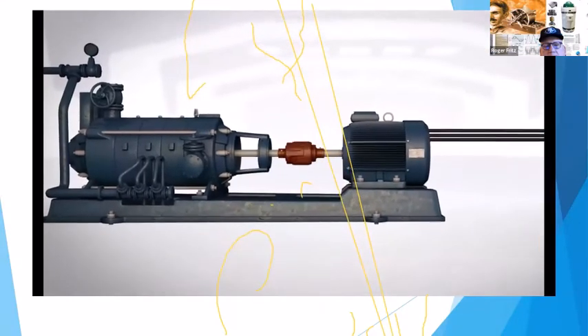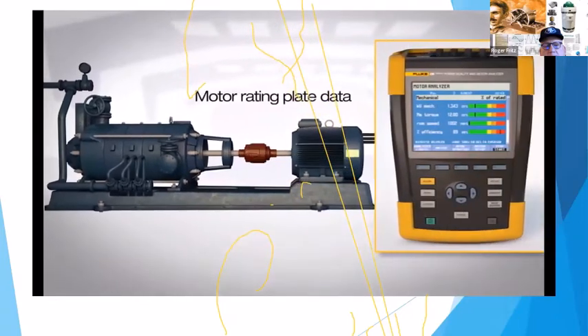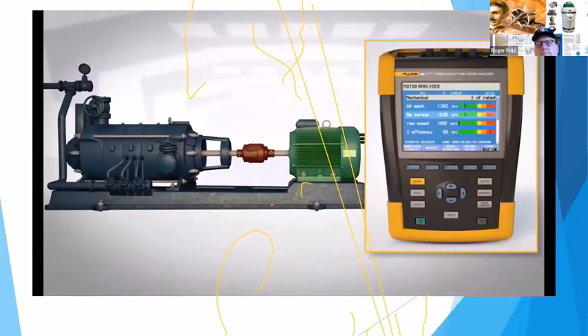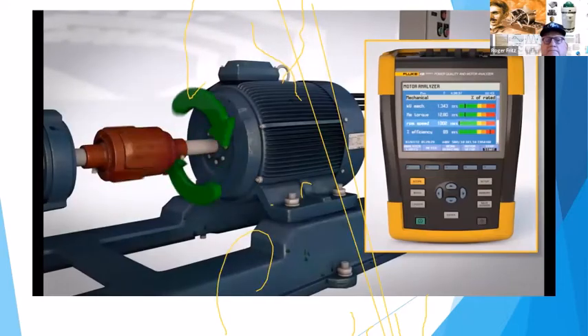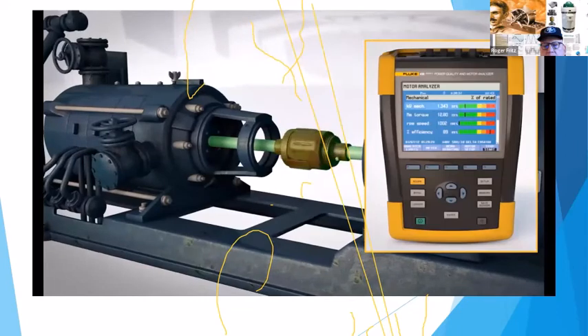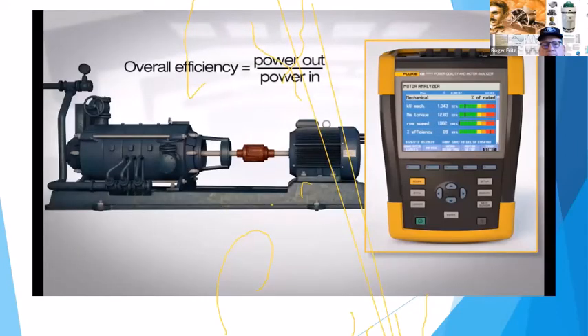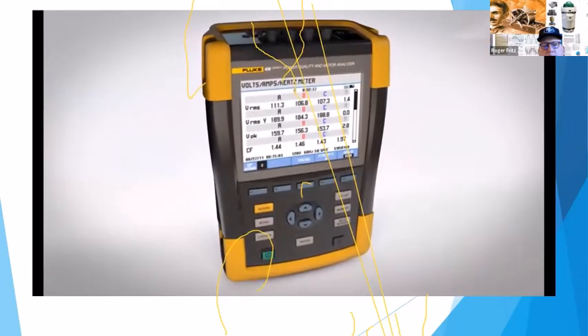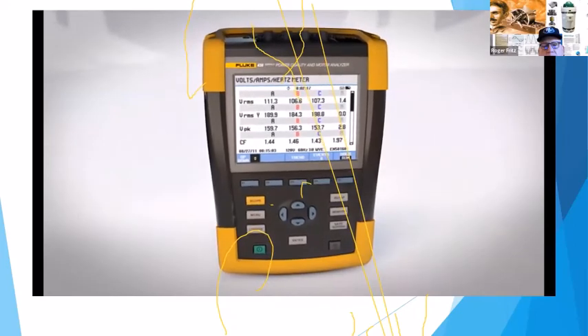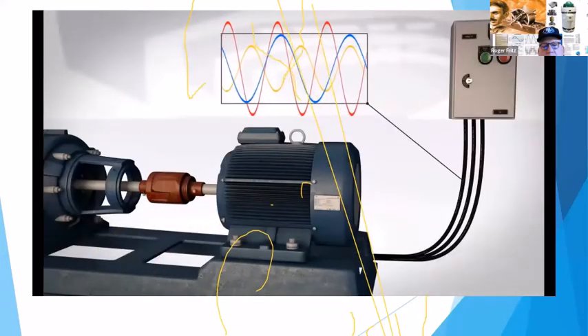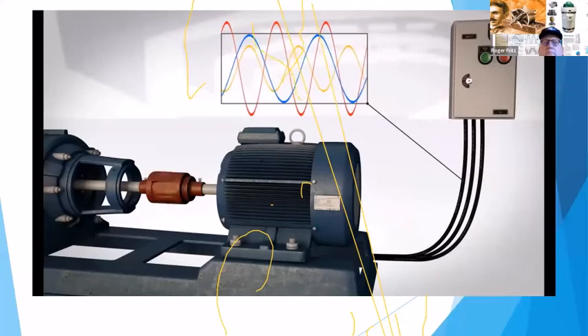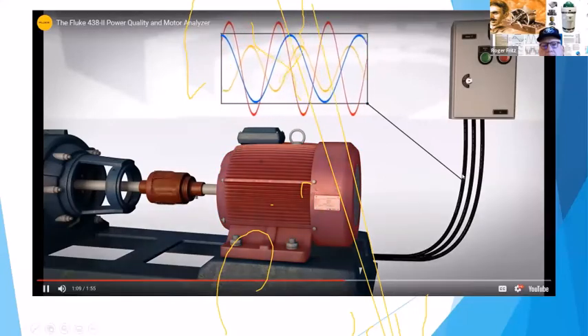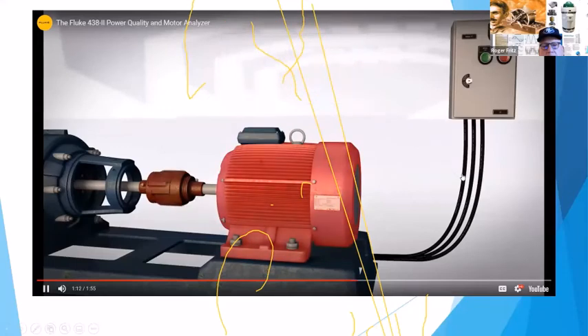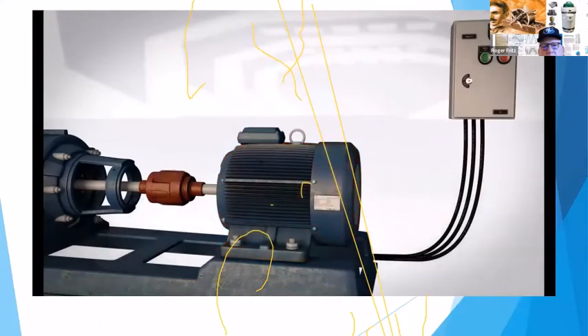Using three-phase electrical measurements on the input and motor rating plate data, the 438 calculates torque, the most critical mechanical performance variable, speed, load on the motor shaft, and overall efficiency, without the need to install mechanical sensors. All this with a single tool, and all while the motor is running so you don't sacrifice uptime. Power quality issues, such as unbalance and harmonics, can cause motors to run hot, eventually stressing windings and accelerating failures. Motor failures lead to costly downtime, and the cost of waste associated with inefficient motors adds up.